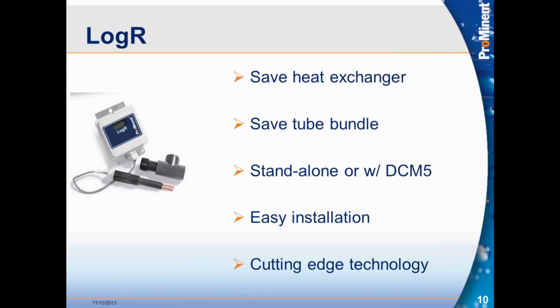And so they're spending thousands and thousands of dollars in equipment costs and repair costs in order to take care of these heat exchangers, these tube bundles that have gone bad because of corrosive conditions. Well, what the Log-R will do is watch that metal and let an operator know when the water becomes corrosive to that certain metal. It won't tell an operator why it's corrosive, it just tells the operator that it is. And this is huge because it at least gives the operator a chance to do something about it.